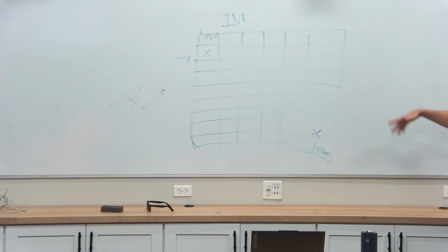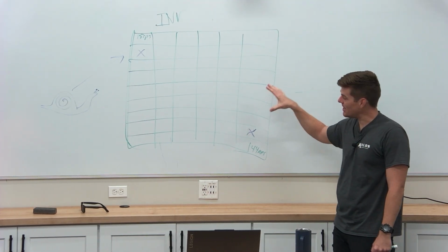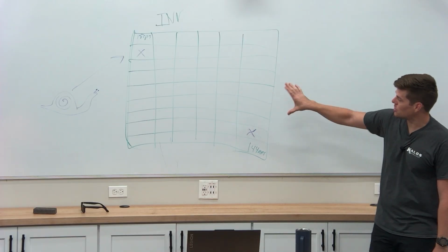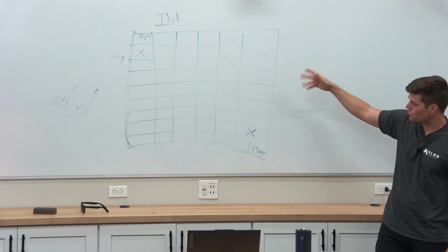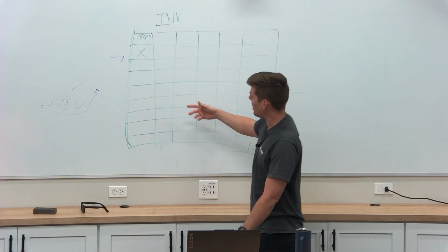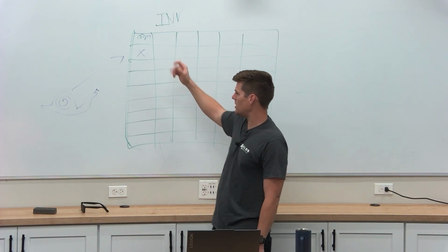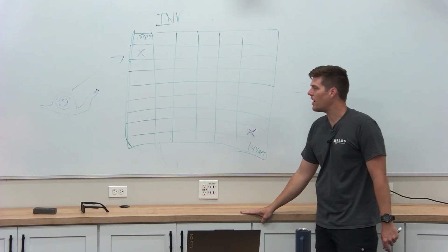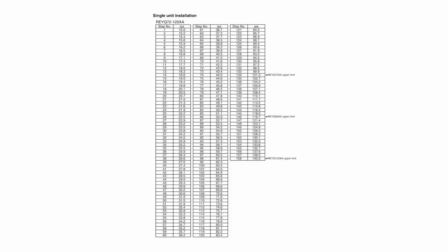So you've got your speeds. This is a diagram we have access to in our actual service manual, and it shows you all these different speeds. I know, because I looked at my service manual, that if I'm at this speed here, let's say that's 17 RPS, my compressor is running really slow, which means there might be some drastic temperature changes throughout the system because of that.